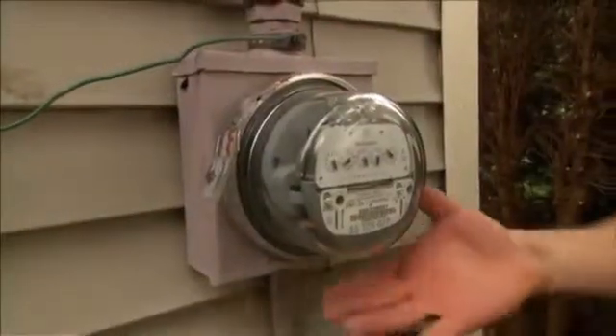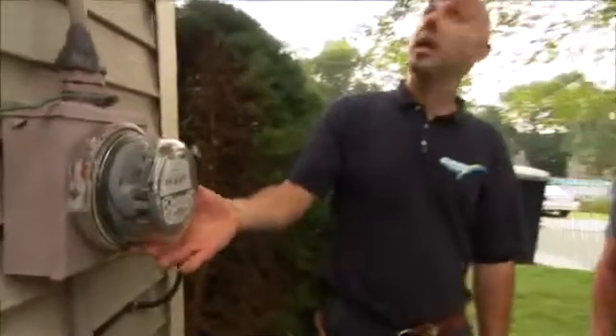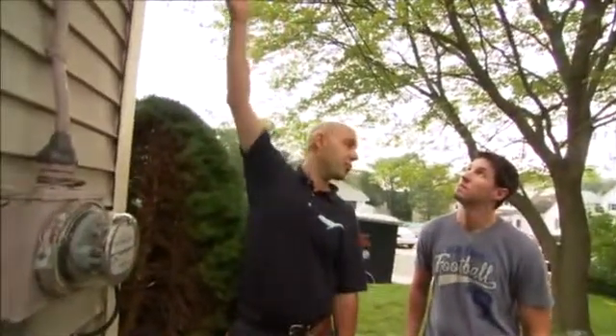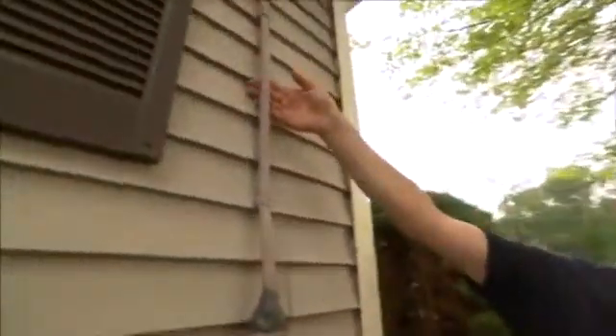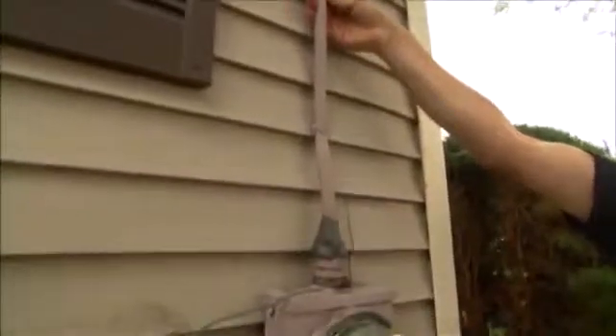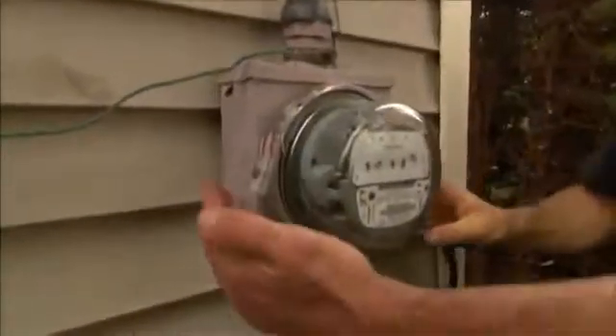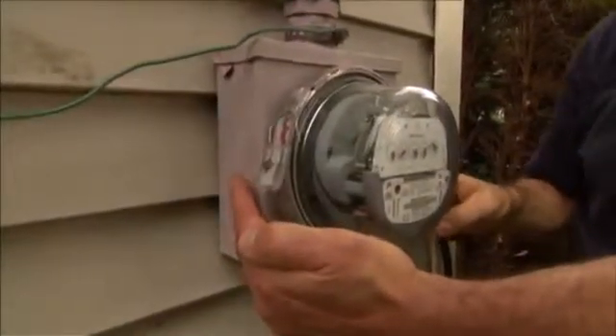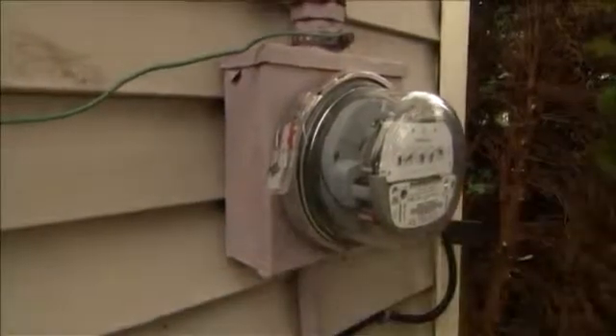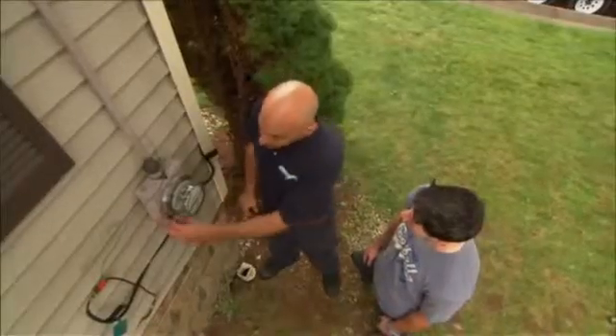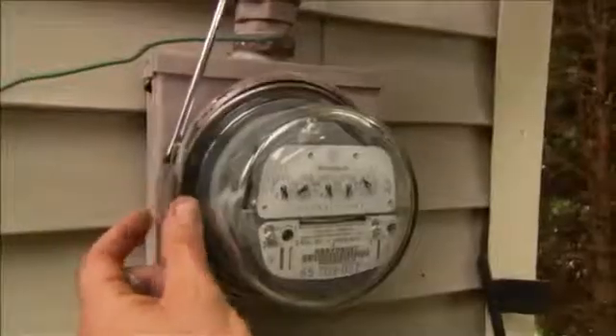The power company owns this glass meter and the wires coming in from the street. Everything else is your responsibility as the homeowner, including the cable providing power to this metal enclosure, called a meter socket. Now with the power off, I'm going to remove the glass meter from the meter socket.